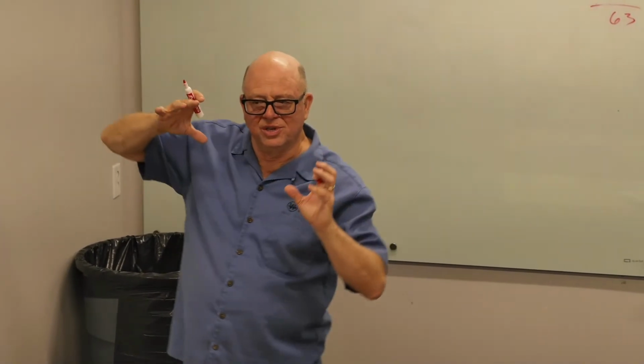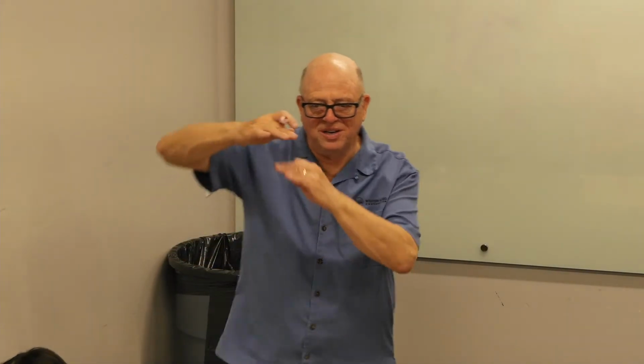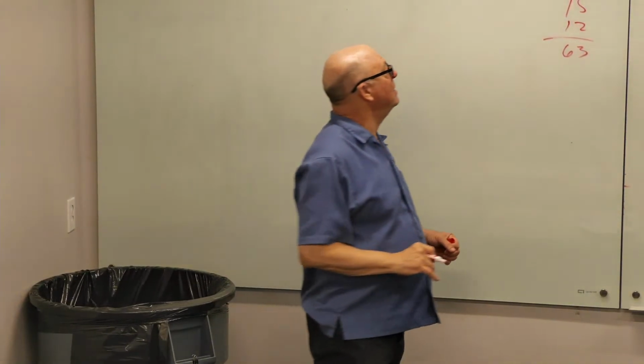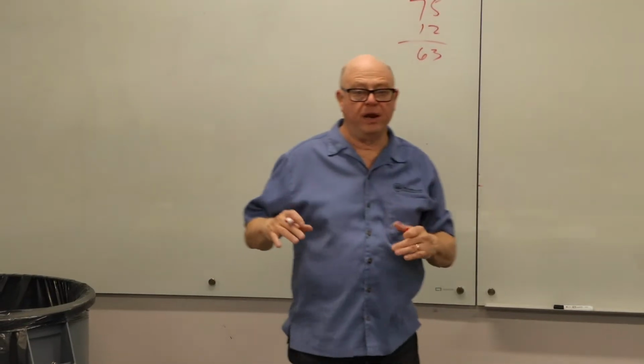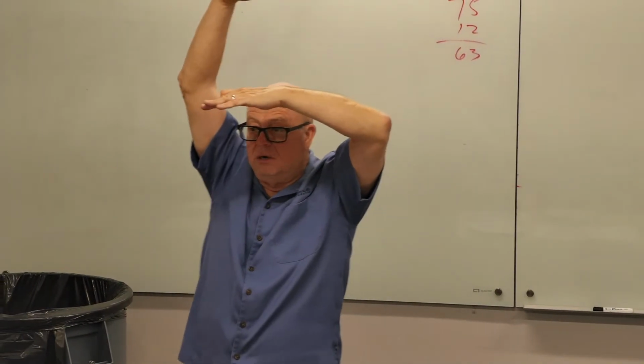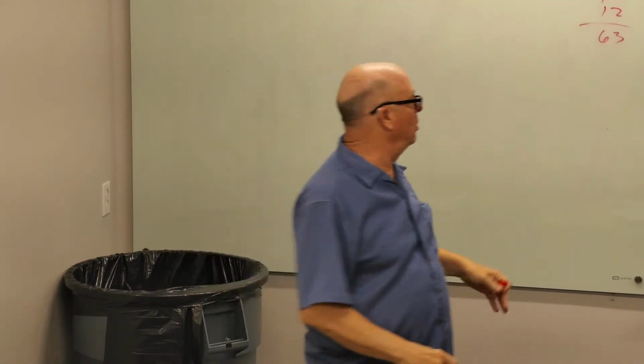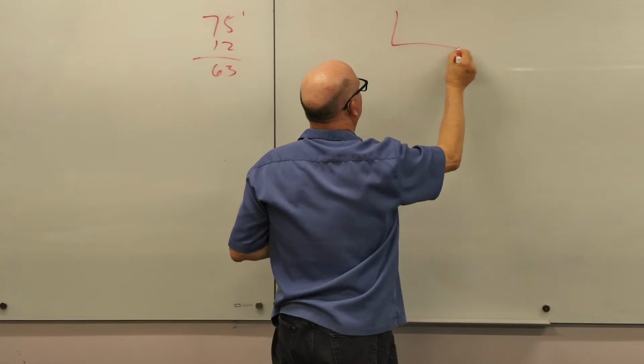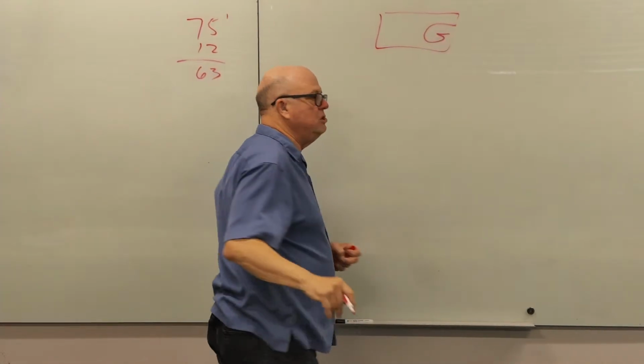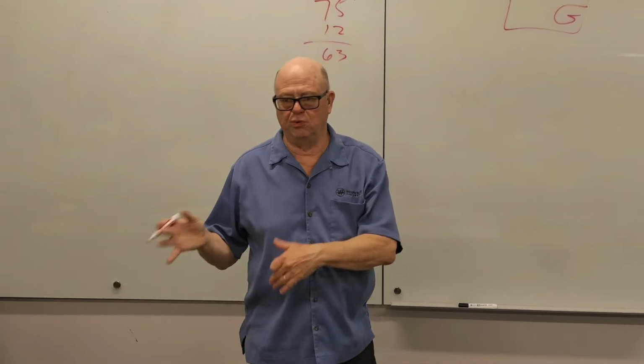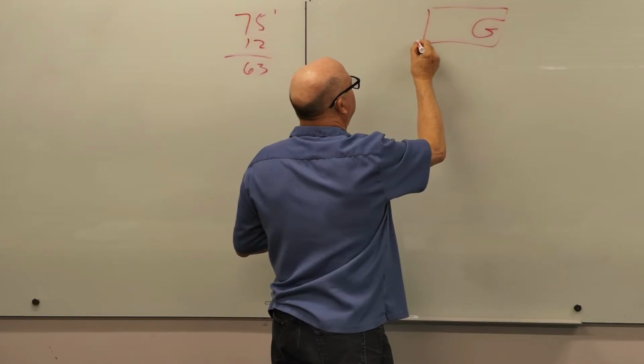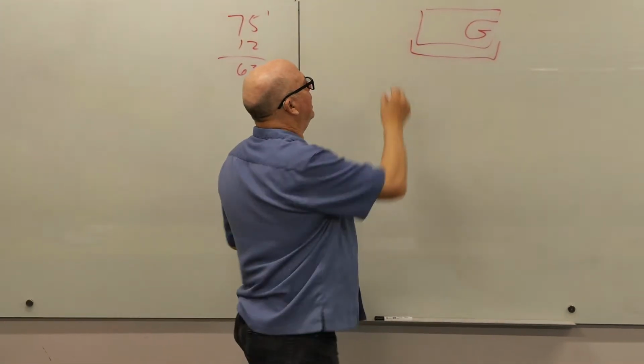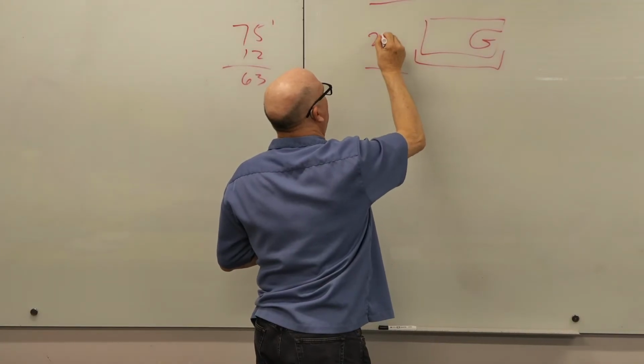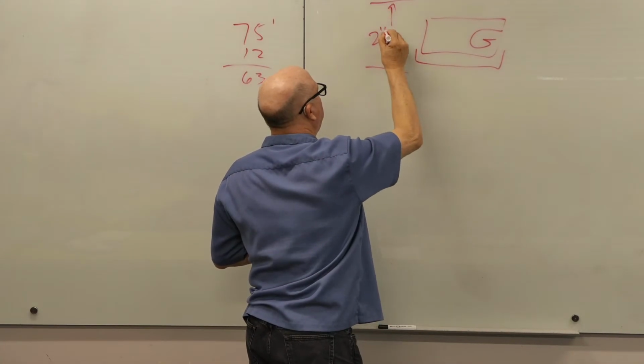Whether I get 5 floors or 6 floors out of that building relates directly to how much ceiling space I'm going to leave myself. And how much more leasable space do I get if I have one more floor, right? So you end up a lot of times today with a fairly cramped ceiling. So let's say that I'm doing this building for this general contractor and I got water source heat pumps. That's a cheap, reasonably efficient way to do things. It has other drawbacks, but it's not bad. Okay. And I got an auxiliary drain pan underneath. And I've only got a little over 2 feet. I don't know, maybe I got 2.5.